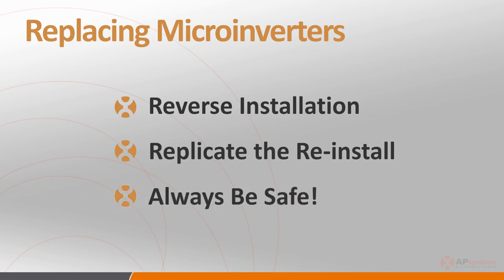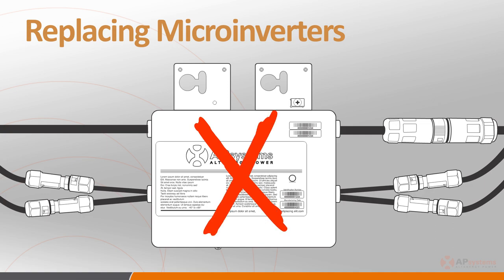You'll also need to verify that the inverter UIDs have been correctly entered into the ECU. A flashing red LED is an indication that the inverter is not producing power — check the DC and AC leads to be sure they are securely connected. A solid red LED indicates the inverter has detected a ground fault. For the most part, replacing the microinverters is as simple as reversing the installation process for removal and replicating it for reinstallation, with a few extra steps added for your safety.